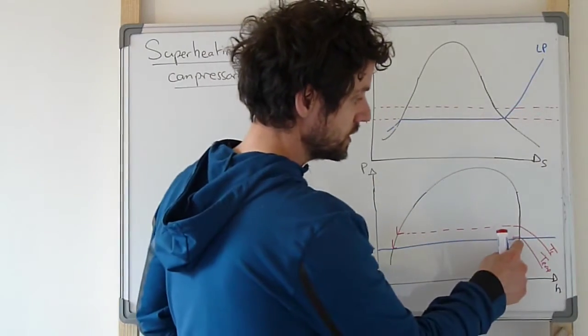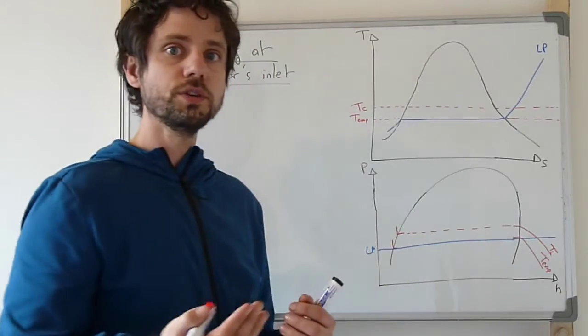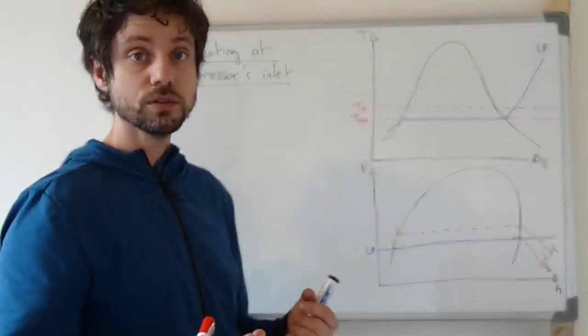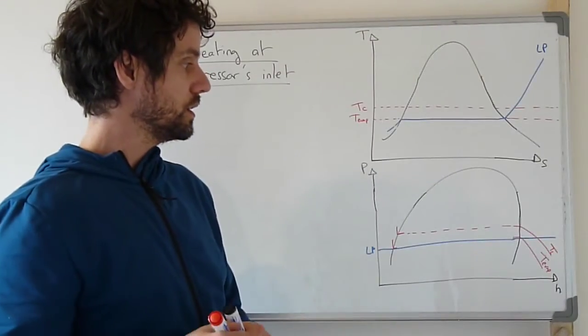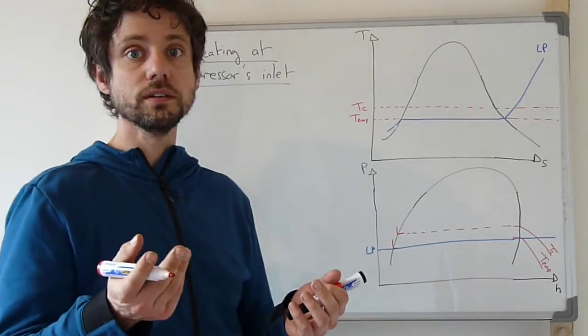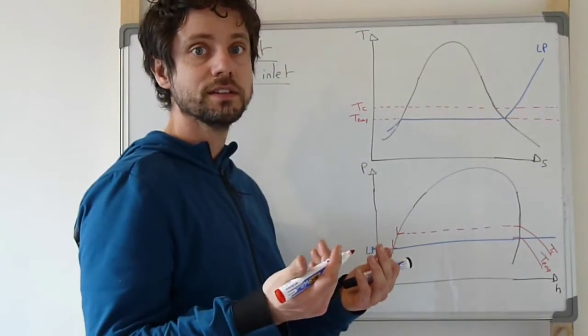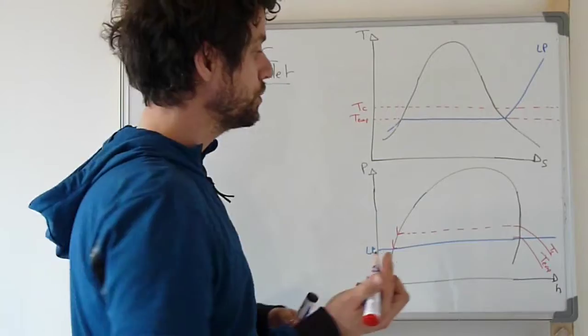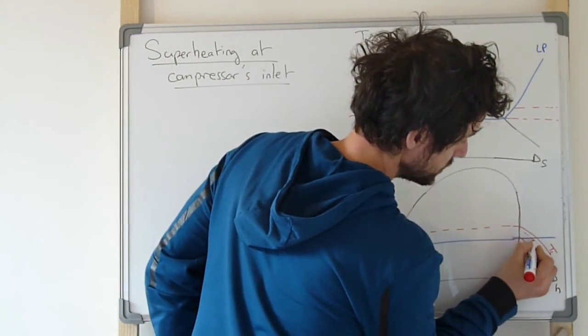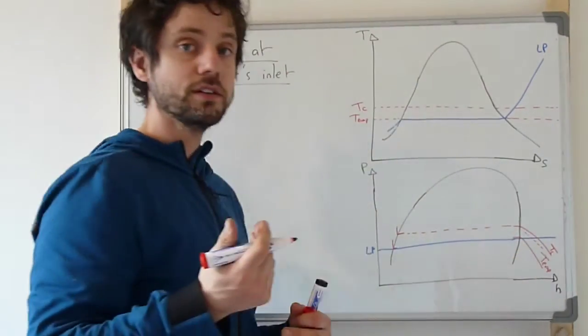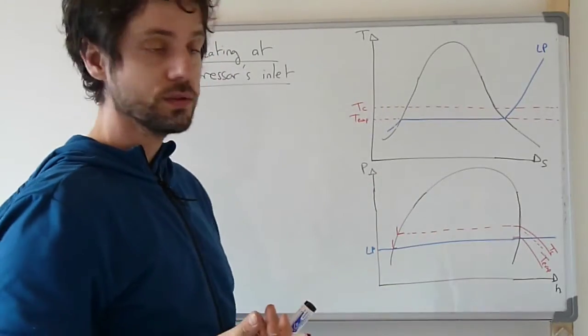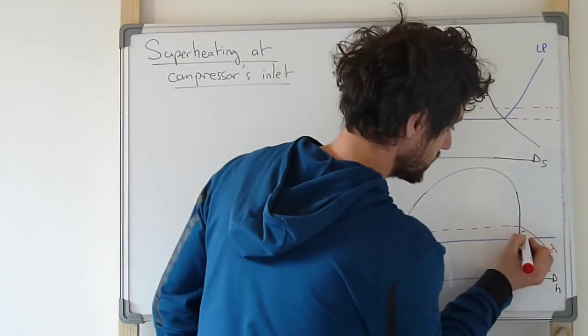We cannot go beyond the cold temperature, so the temperature of the cold source. So usually the superheat will fix an inlet temperature of the compressor that is somewhere between the evaporator temperature and the cold source temperature. So somewhere there, for example.